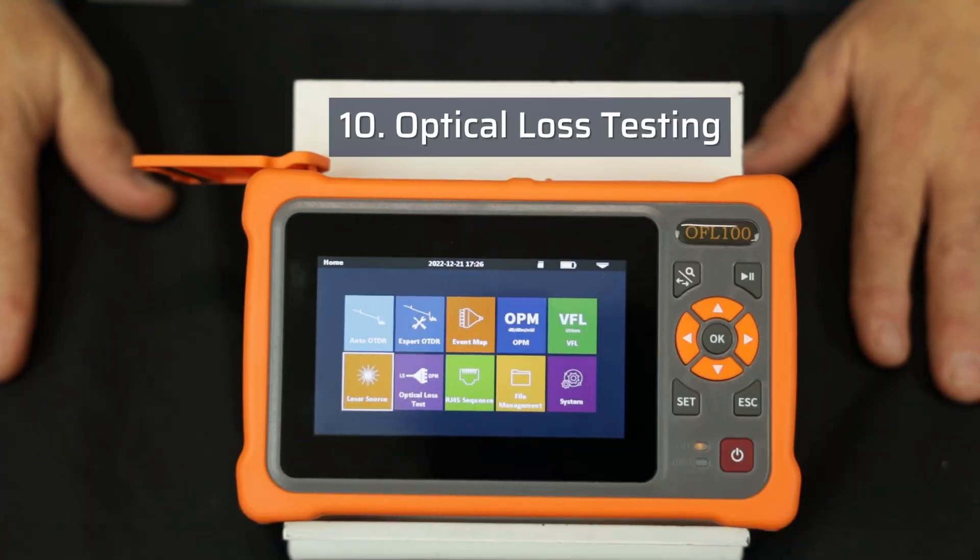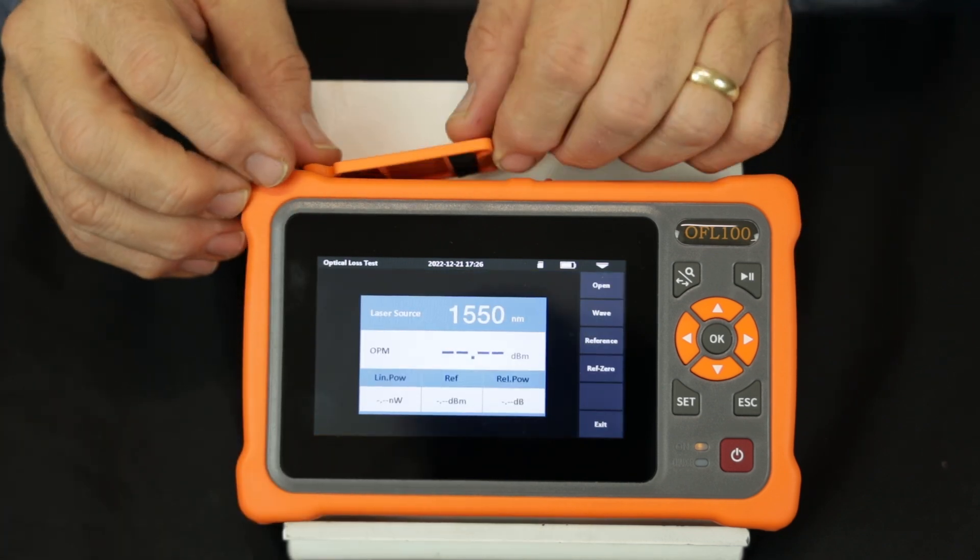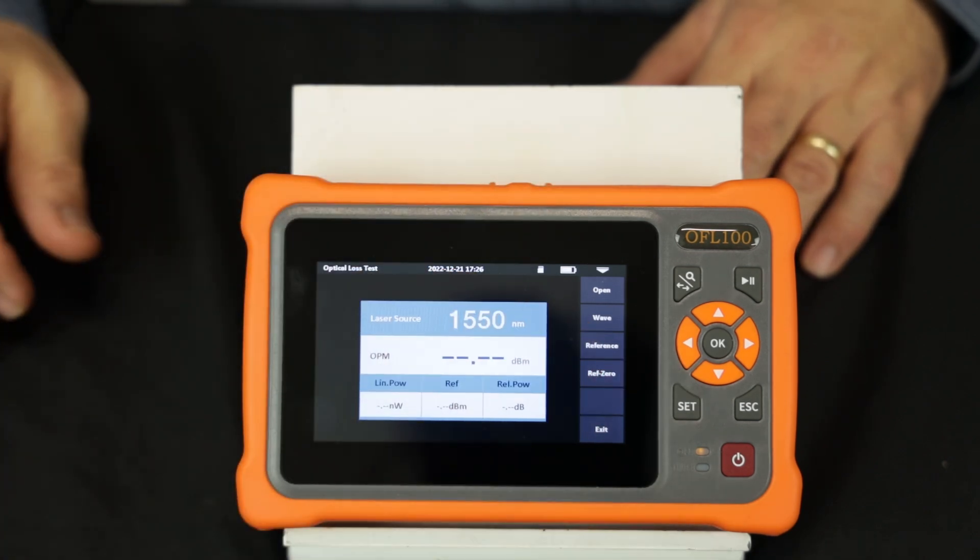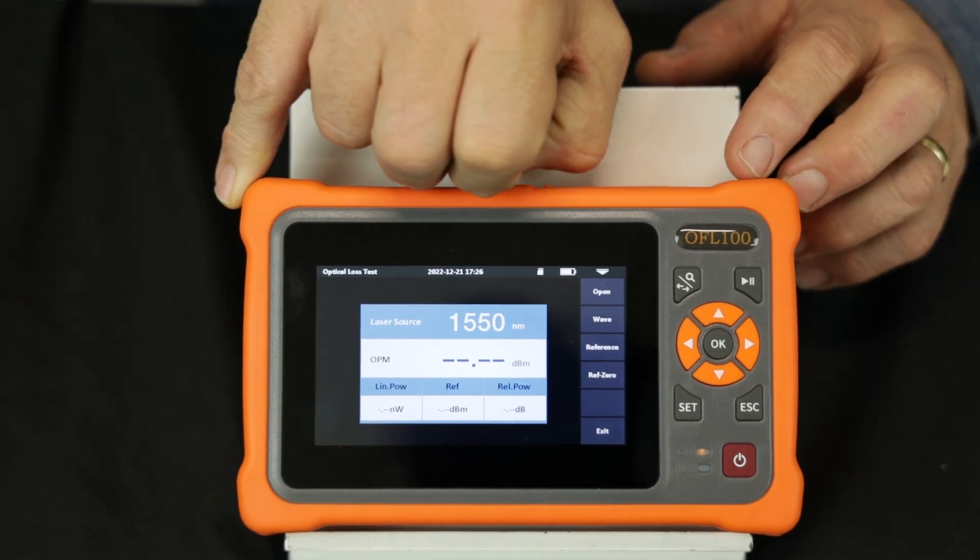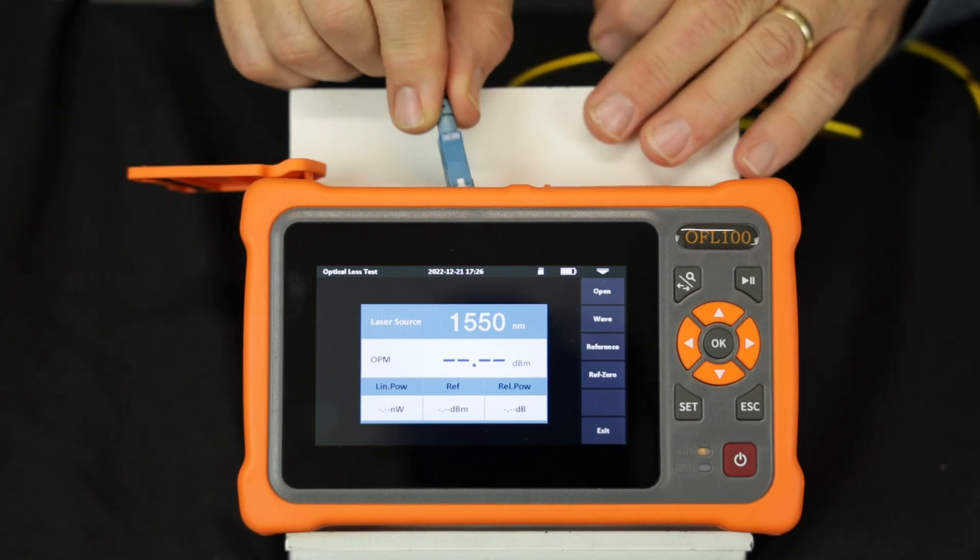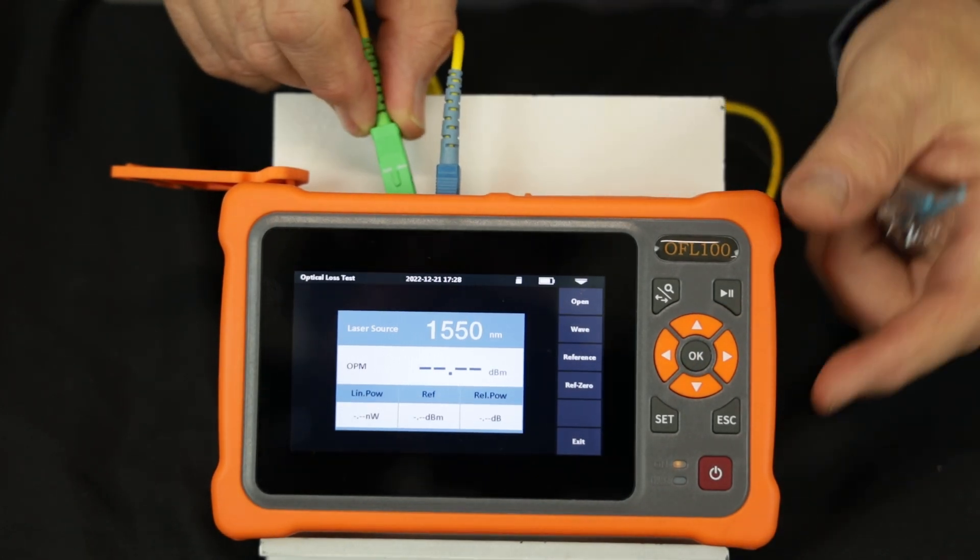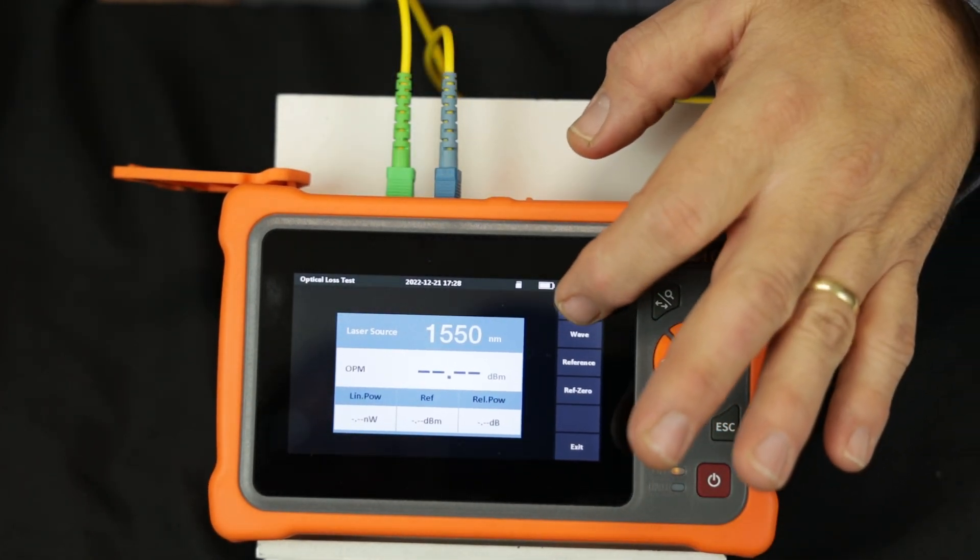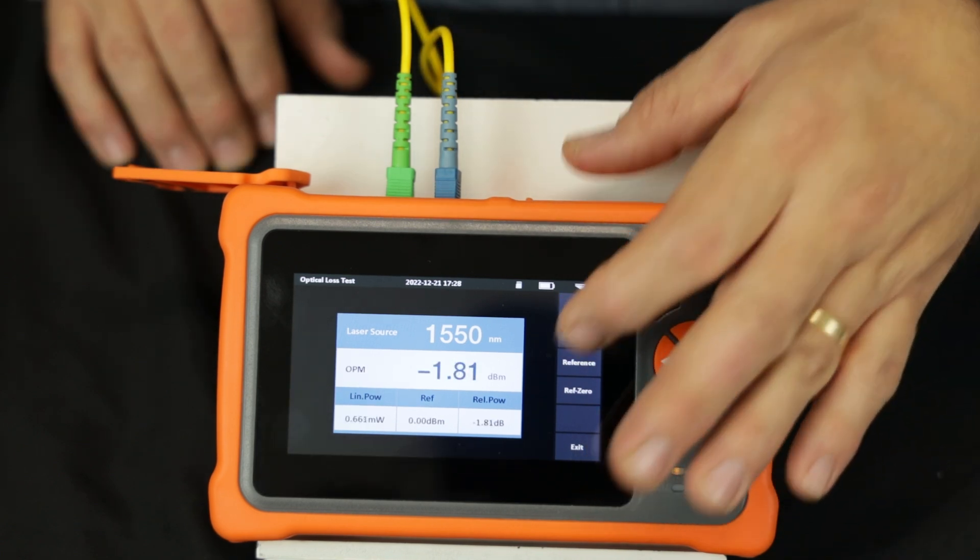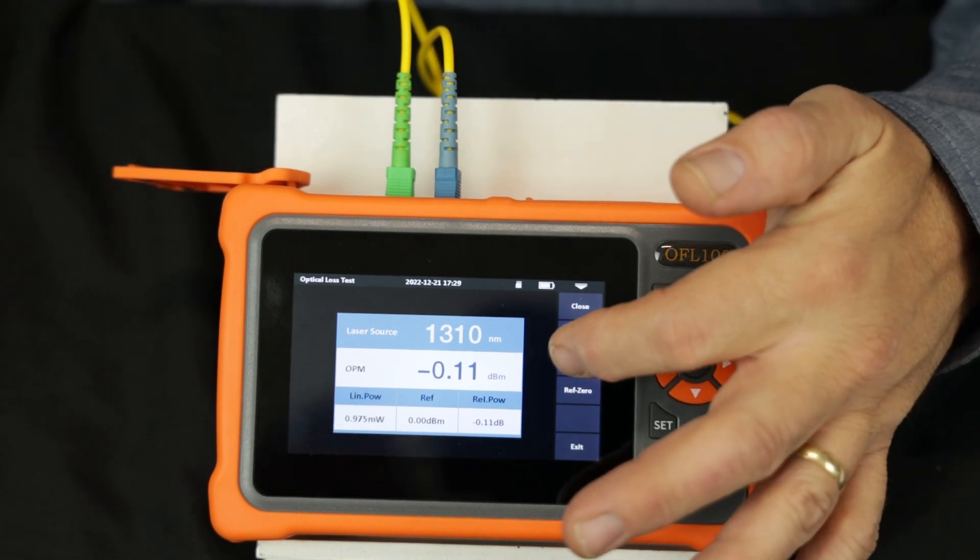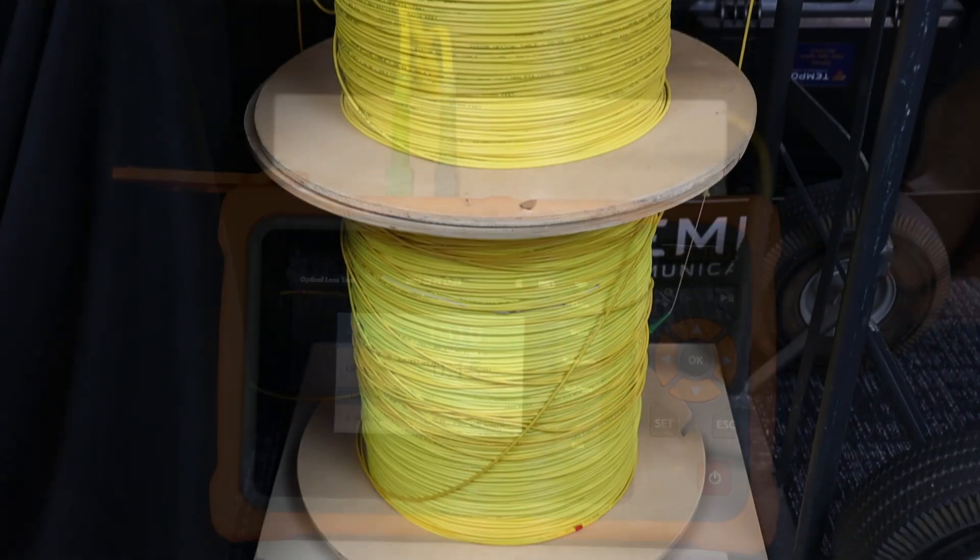Select the optical loss test from the main menu. The optical loss tester allows the technician to measure the loss of a fiber optic cable or optical device. The technician can select the reference 0 with the dust cap closed to null out any dark current from the detector diode. A patch cord is connected to the OPM port and then to the OTDR port. Turn the source on and select the desired test wavelength. A reference for 0 dB can be made by pushing the reference key. 0 dB is displayed as the relative power.